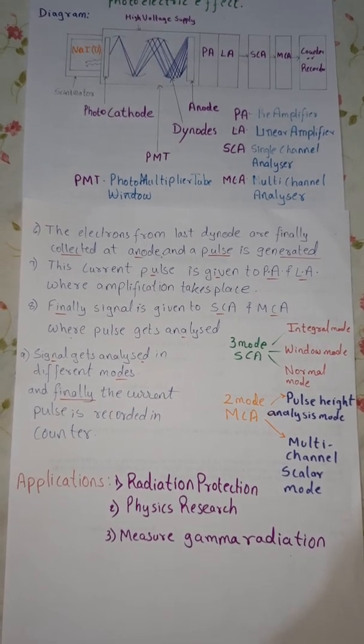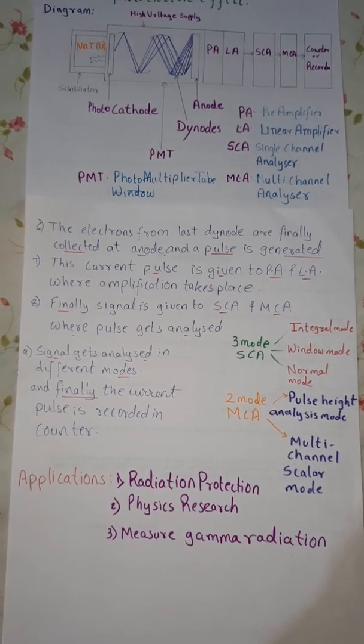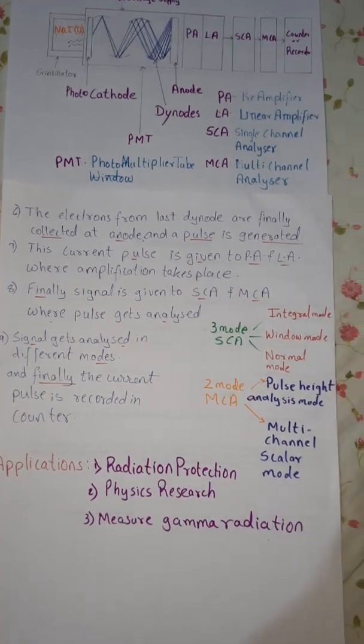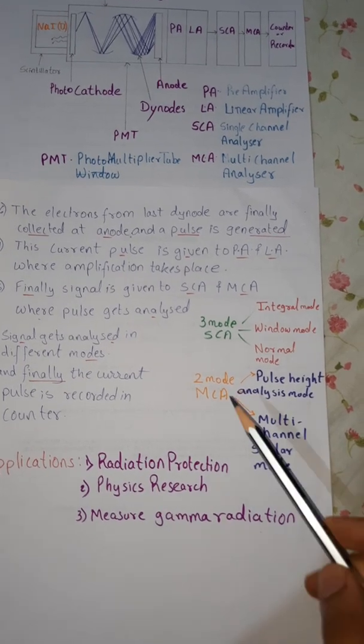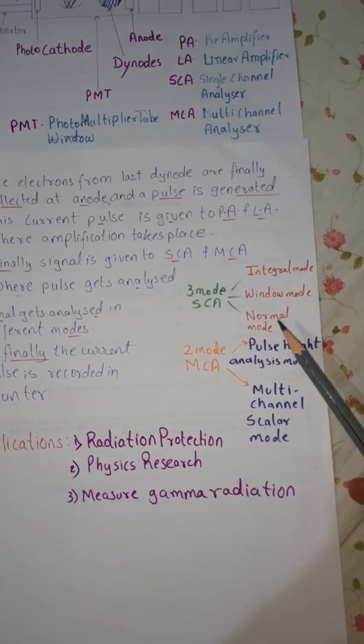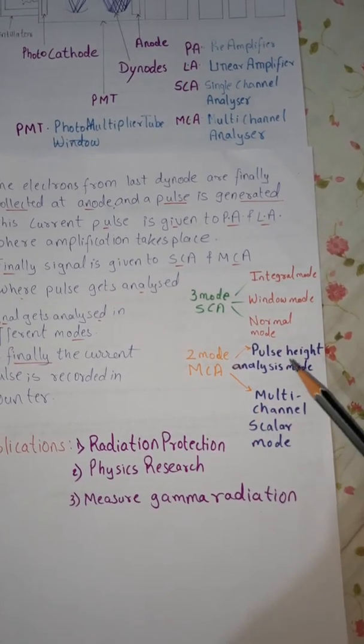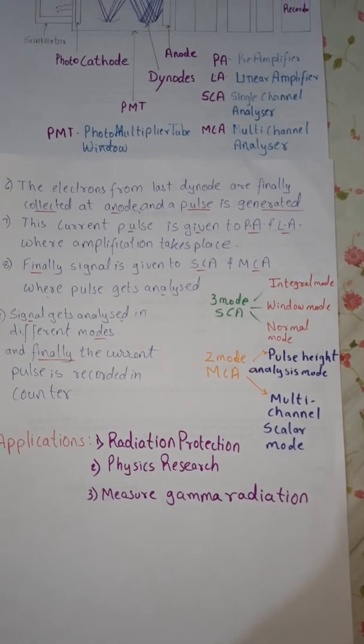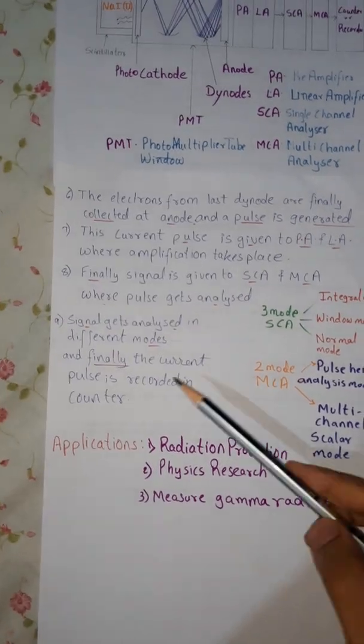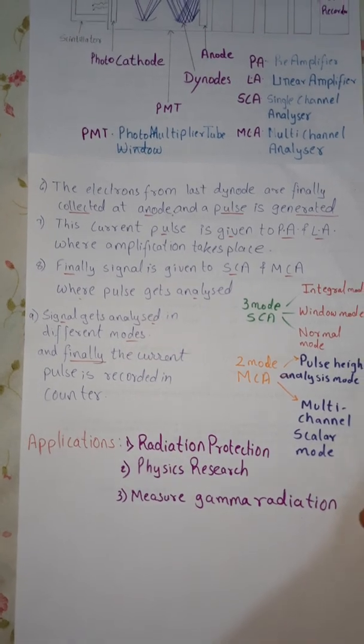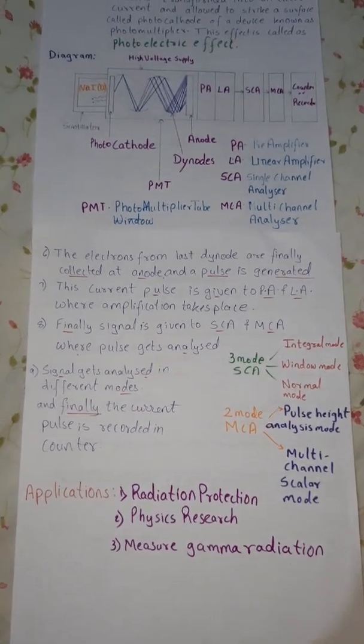The electrons from the last dynode are finally collected at anode and a pulse is generated. This current pulse is given to the amplifiers where amplification takes place. Finally signal is sent to the analyzers where pulse get analyzed. For SCA there are three types of modes: integral mode, window mode, and normal mode. For MCA there are two modes: pulse height analysis mode and multi-channel scalar mode. This signal gets analyzed in different modes and finally the current pulse is recorded in the counter.